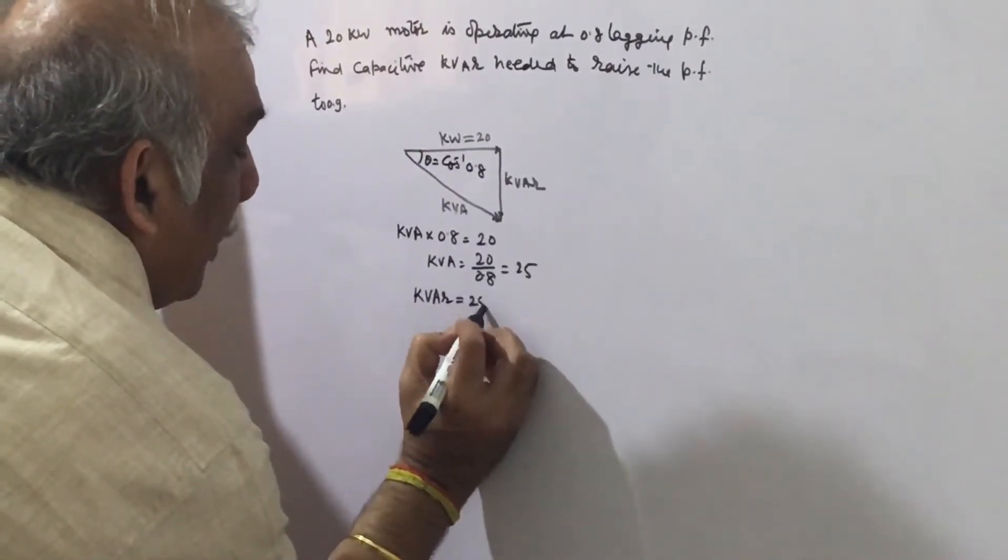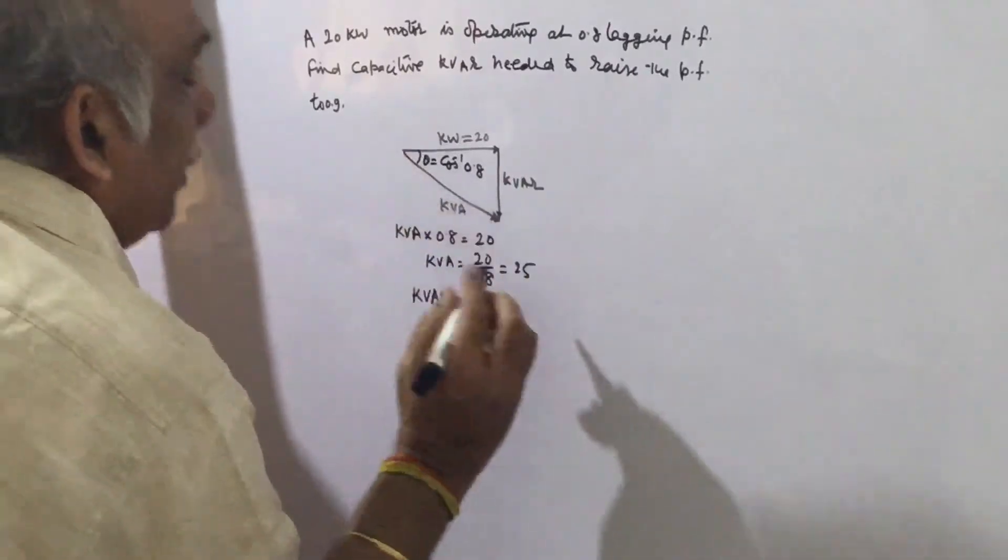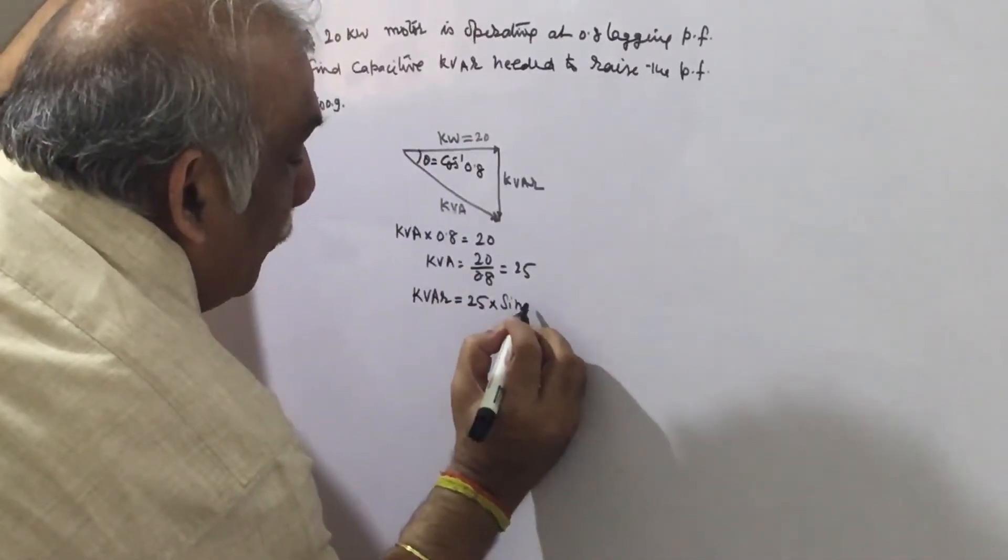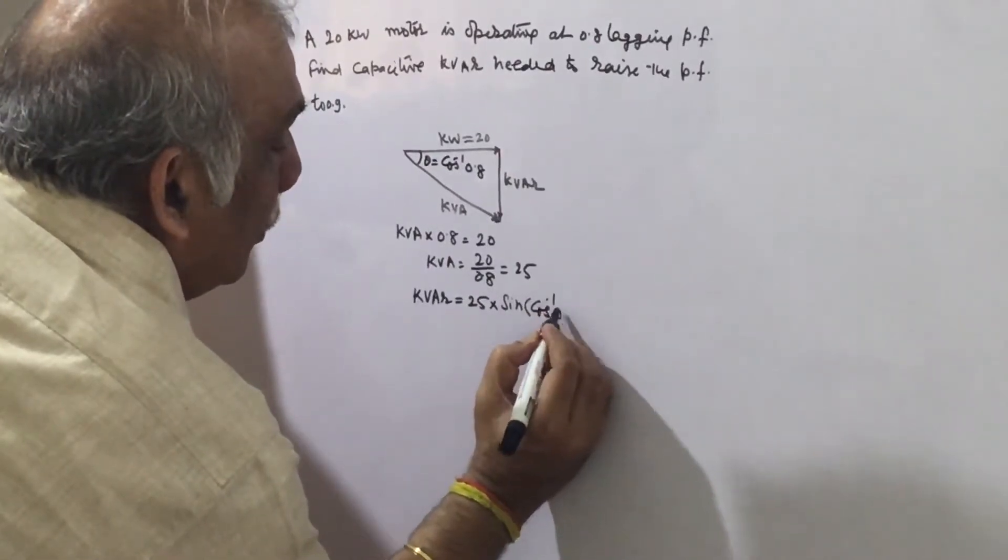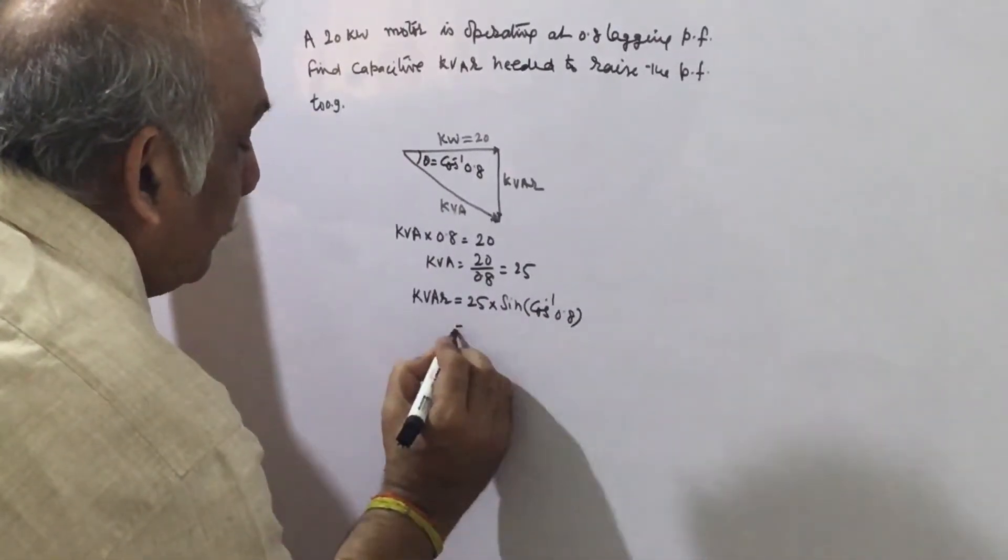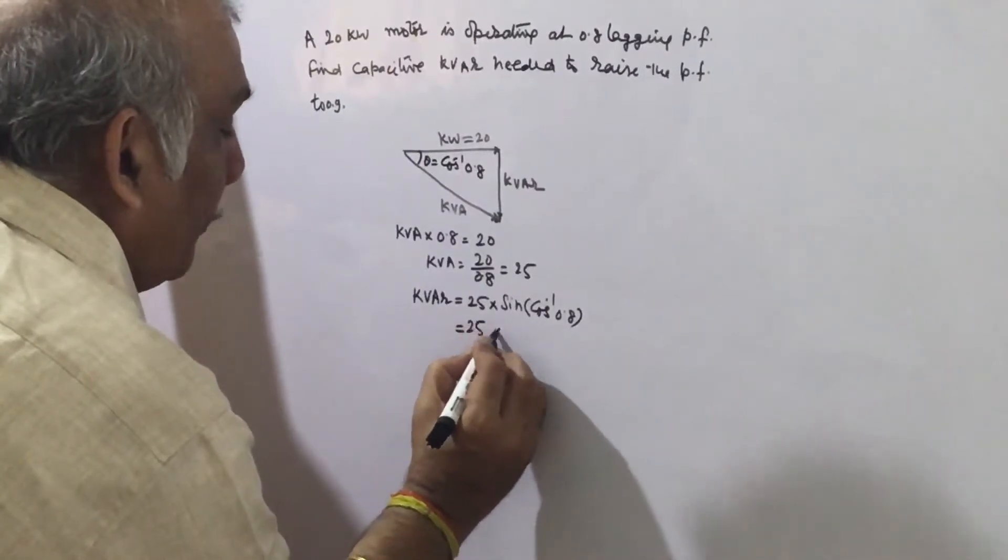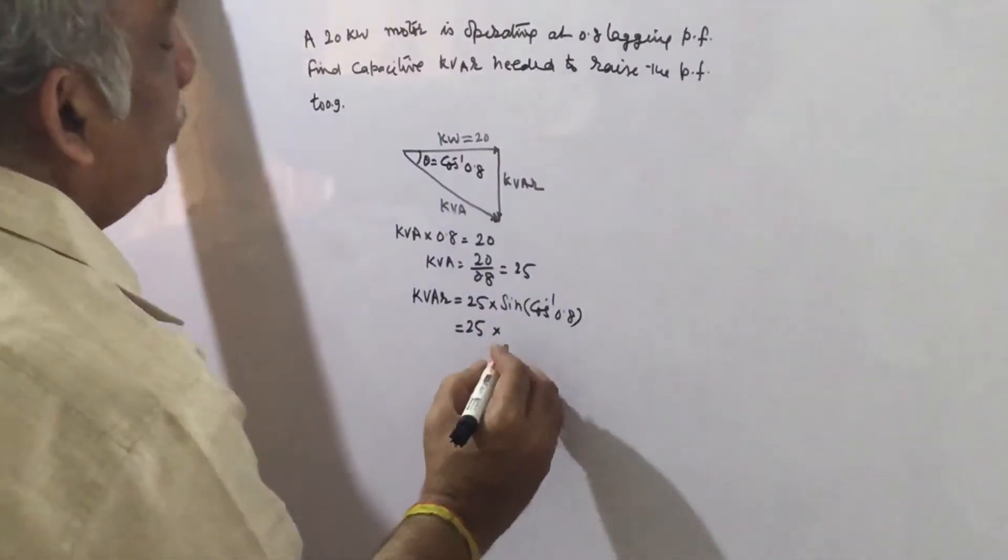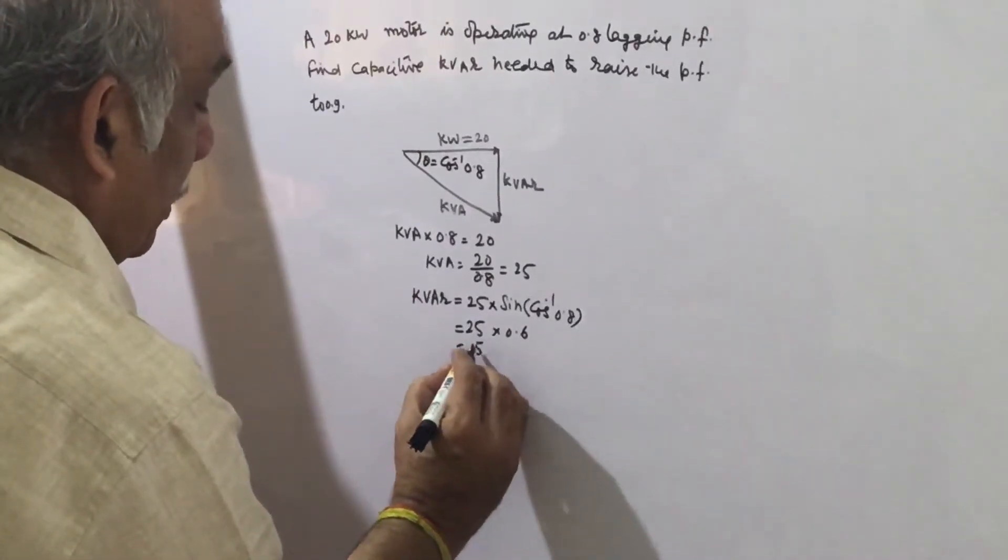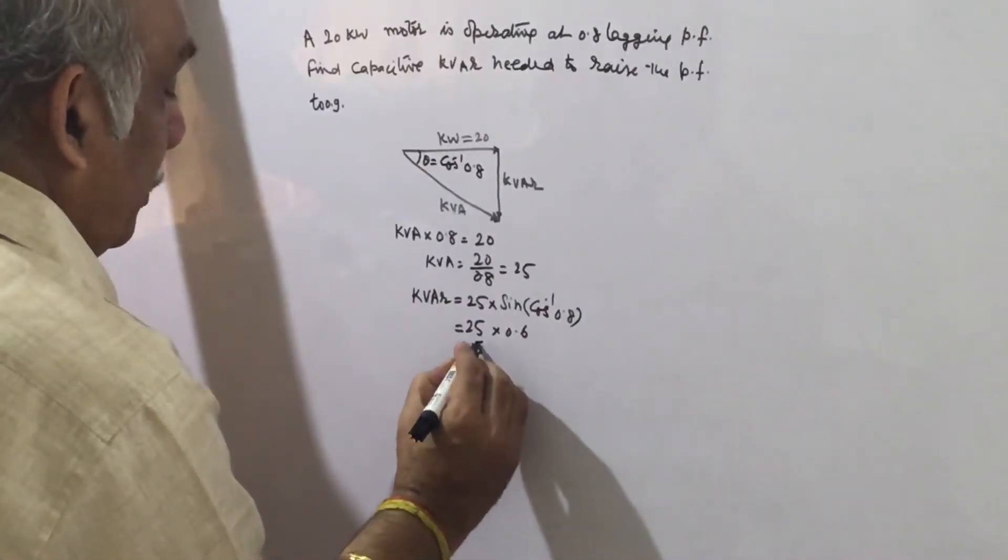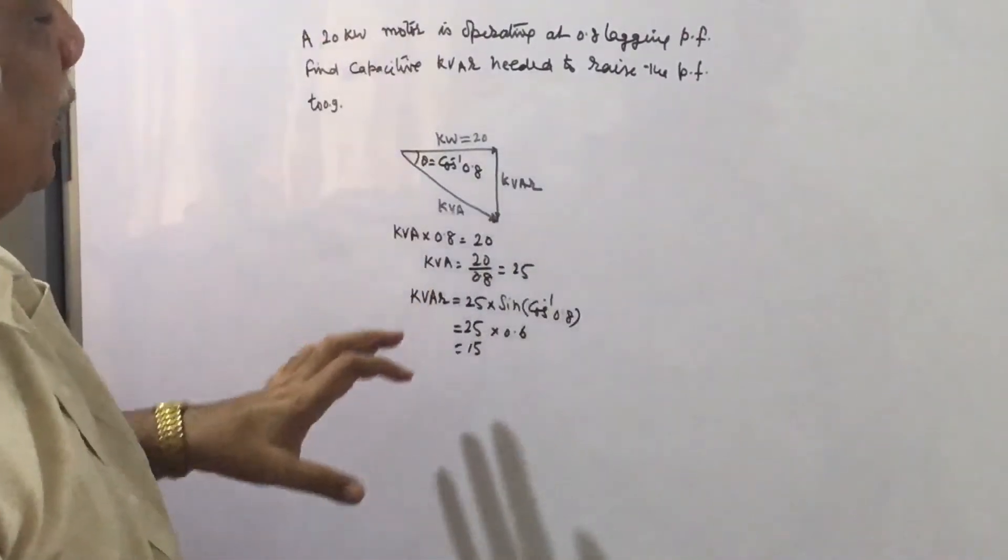And kVAR is equal to 25 times sine of this angle, that is sine of theta. Theta is cos inverse 0.8, so 25 times 0.6 gives us 15 kVAR. When the motor is operating at 0.8 power factor, it is drawing 15 kVAR.